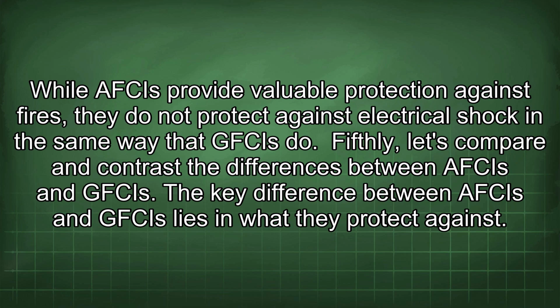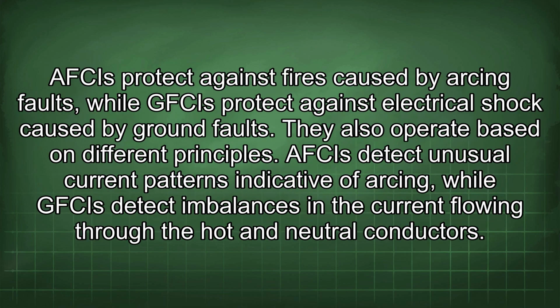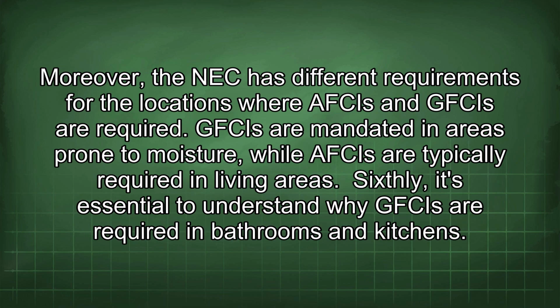Fifthly, let's compare and contrast the differences between AFCIs and GFCIs. The key difference between AFCIs and GFCIs lies in what they protect against. AFCIs protect against fires caused by arcing faults, while GFCIs protect against electrical shock caused by ground faults. They also operate based on different principles. AFCIs detect unusual current patterns indicative of arcing, while GFCIs detect imbalances in the current flowing through the hot and neutral conductors. Moreover, the NEC has different requirements for the locations where AFCIs and GFCIs are required. GFCIs are mandated in areas prone to moisture, while AFCIs are typically required in living areas.